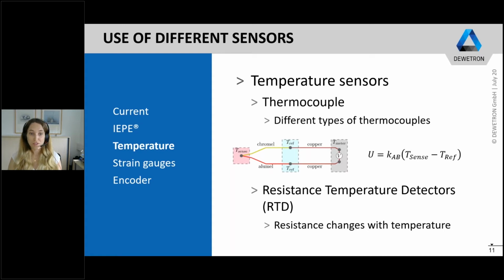The resistance temperature detectors are based on the principle that the resistance changes with temperature, and usually there's a linear relationship which is used for the measurement. These detectors or sensors are more accurate. They are also more expensive, and they go up to about 600 or even some up to 800 degrees Celsius.